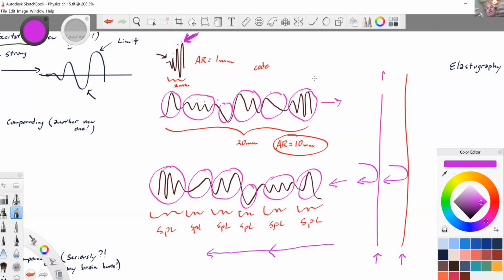And the best way to get rid of the noise is to increase the signal. When you increase the signal, the real echoes, the echoes you want to see, stand out. When you increase the power, the ratio of good signal to ugly mess goes up, and so you get a better image overall. It becomes easier and easier to ignore the noise when the real signals are powerful. So by being a more powerful signal, coded excitation creates a better overall image, higher signal to noise ratio, improved axial resolution.